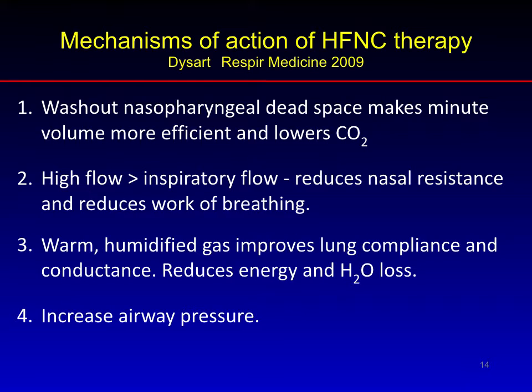So there's fresh gas, completely washing out the upper airway. So as the baby breathes, it's getting fresh gas from just above the larynx. And so that makes the breathing, the minute volume, much more efficient. CO2's a bit lower, and it reduces the whole nasal resistance because that's been bypassed by all the flow. And one of the questions that gets asked is, well, what flow should we use? Well, the principle is that the flow should be higher than the peak nasal inspiratory flow of the baby. I won't ask you what it is because we don't know what it is, but it's roughly 3-4 litres a minute. And why do you want a higher flow than that?